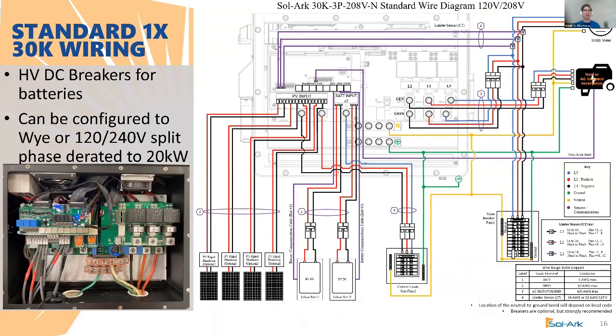So this is what the standard wiring diagram looks like at 120/208 volts. And so you can see the four strings going into the MPPTs. You can see 2 separate battery banks going into each one. So for the 30K, we are able to connect to 2 separate battery banks in terms of brands, voltages, and capacities, right? So as long as they do have those closed loop communications, you'll be able to connect to 2 different battery banks, which is amazing. And through the touch of a button, you can connect one single battery bank to both of those inputs. All you have to hit is parallel BAT1 and BAT2, and the system knows that those 2 are connected to a single battery bank.